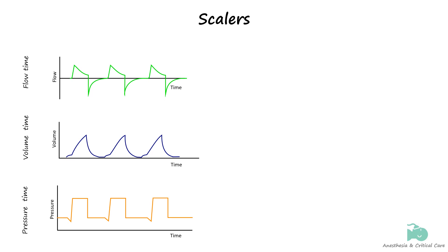Scalars on conventional mechanical ventilators are representations of specific respiratory parameters over time. The three scalars commonly utilized are volume, pressure, or flow plotted on the vertical y-axis against time plotted on the horizontal x-axis. Pressure and flow are measured values, while the volume of each breath is a calculated value. Each scalar represents the entire breath from the beginning of inspiration to the end of expiration.